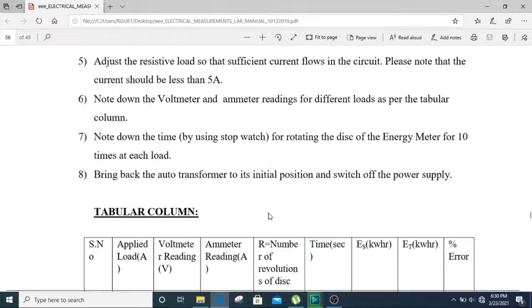By applying different loads like this, you apply a 1 amp load, this will be the reading of the voltmeter, this will be the reading of the ammeter, and you measure the time for 10 revolutions. The number of revolutions will be 10 and the time taken to complete 10 revolutions for the 1 amp load is 41 seconds. Measured energy will be equal to 10 revolutions by 3200 revolutions per kilowatt hour. You are going to get the measured energy.